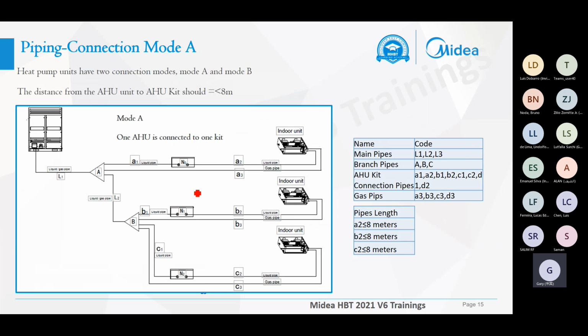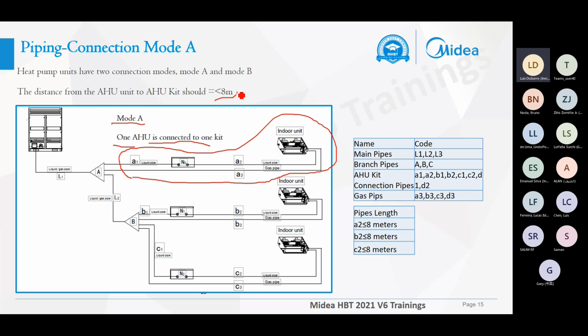For the heat pump unit, we normally have two connection modes. This is mode A. This is one AHU kit connecting to one AHU. This is the very normal way to connect to AHUs. And one thing to be noticed is the distance between the AHU kit and the AHU should be less than 8 meters. You can see the diagram here.